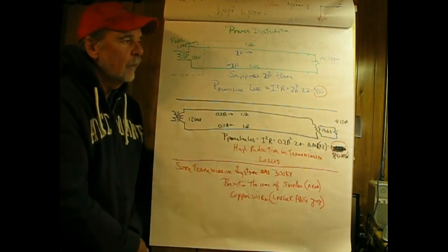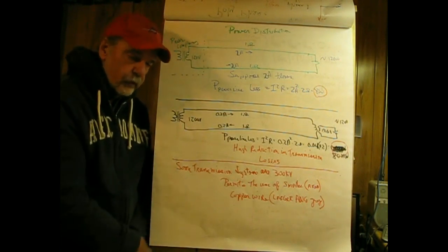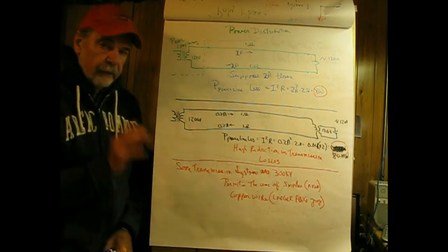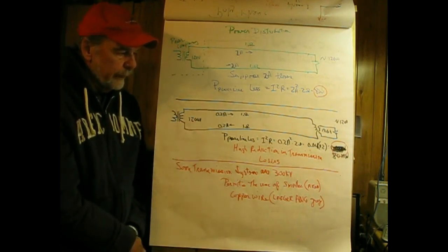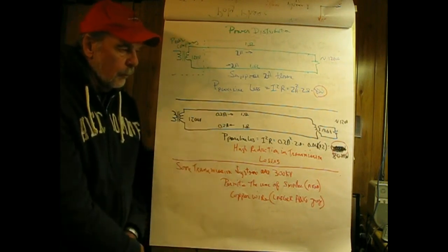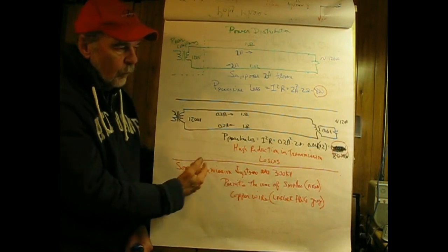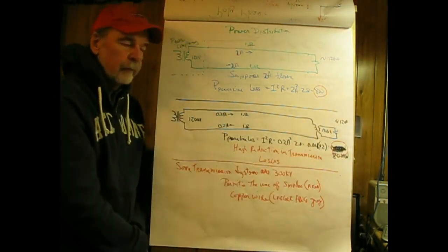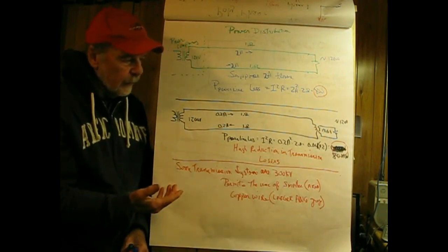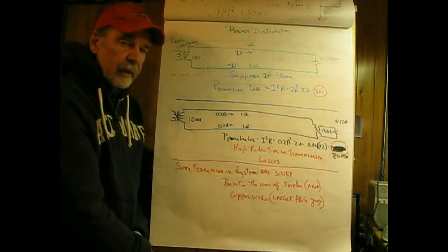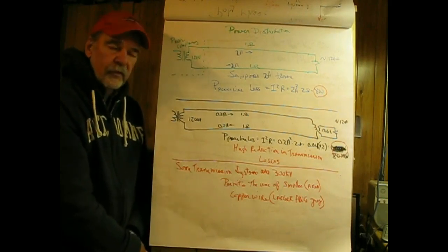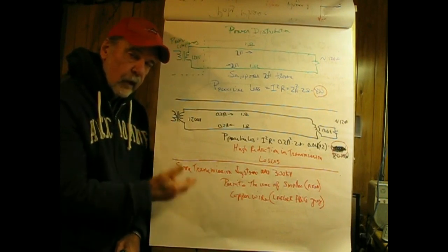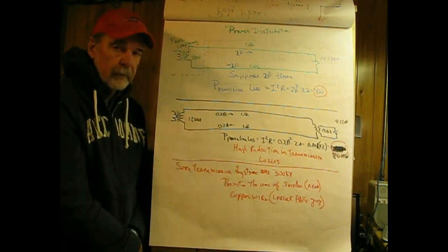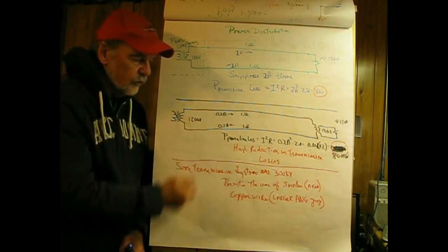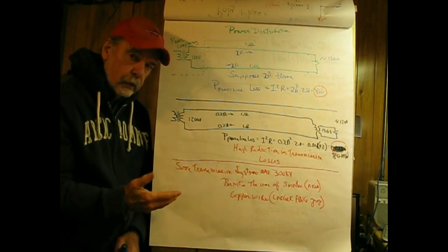Further, the voltage drop would reduce this to less than 120 volts, which wouldn't necessarily be good for us. But if that voltage is stepped up to 1200 volts, the current would then drop to 0.2 amps, and do notice that the same amount of power is being dissipated here, but the power loss, P equals I squared R, when we reduce this, now is 80 milliwatts. So there's a tremendous savings in power line losses if you step the voltage up, because you step the current down, and the power loss in the transmission line is equal to the square of the current.